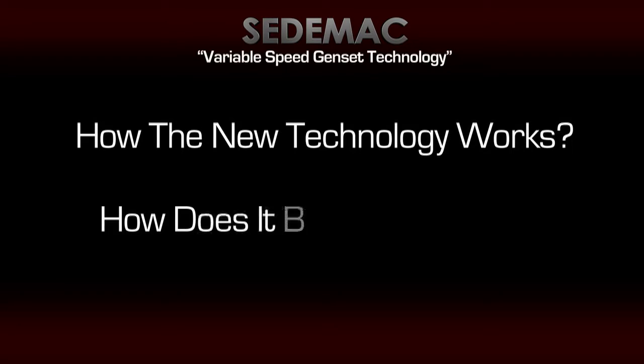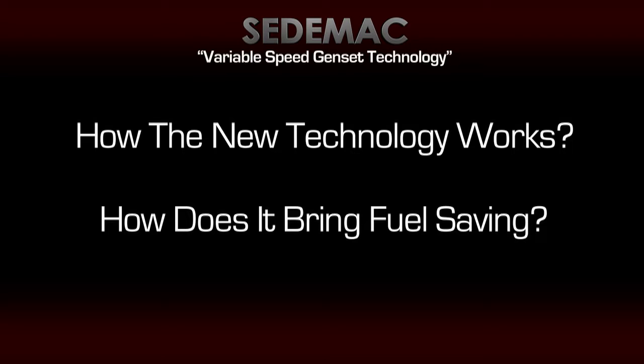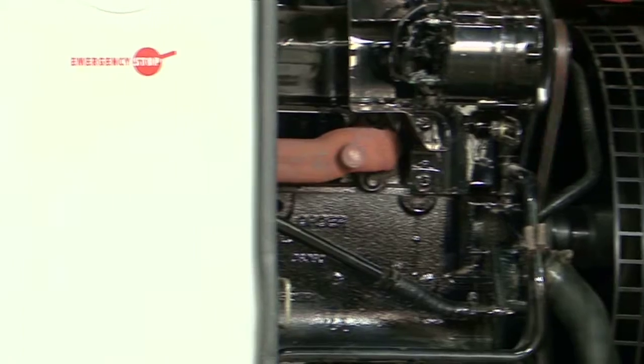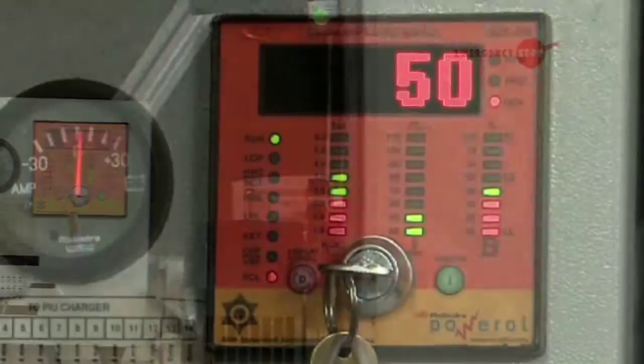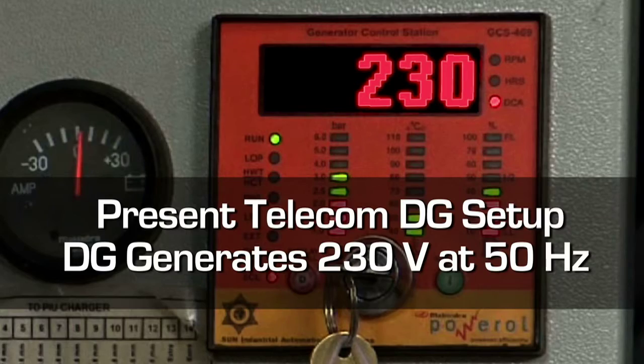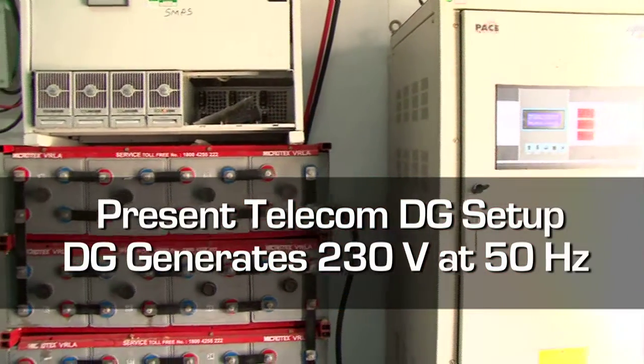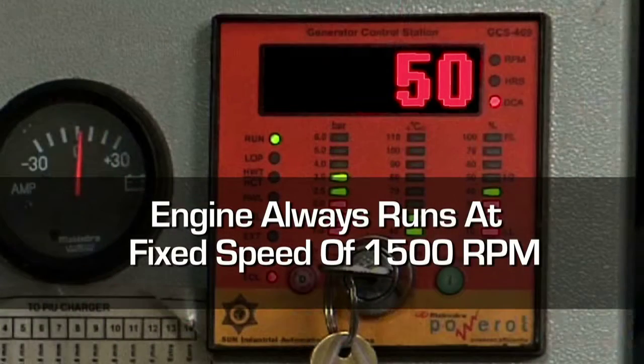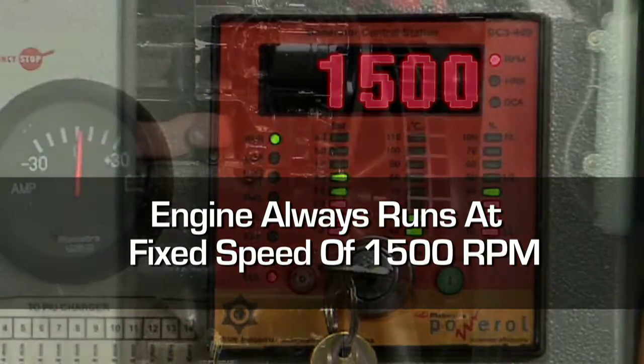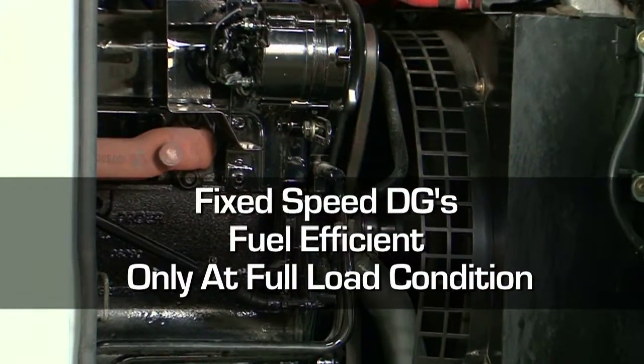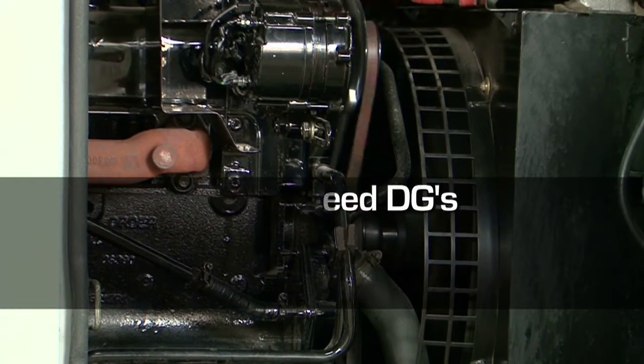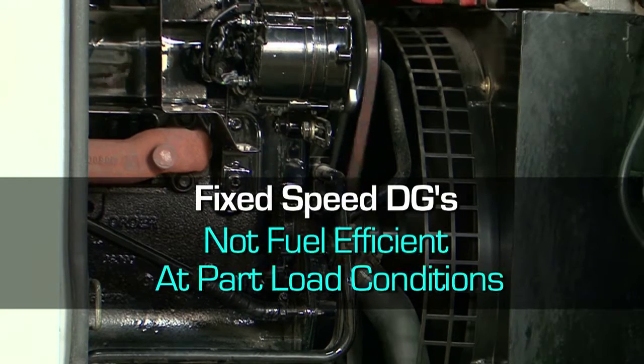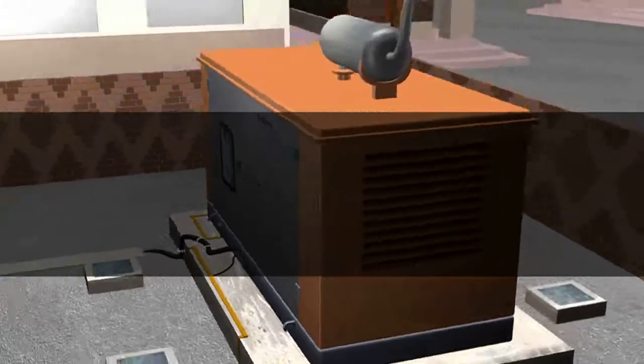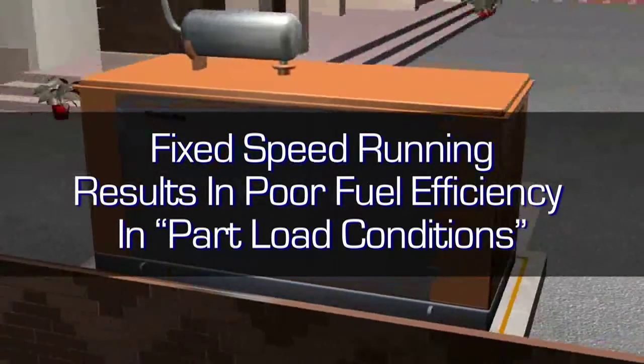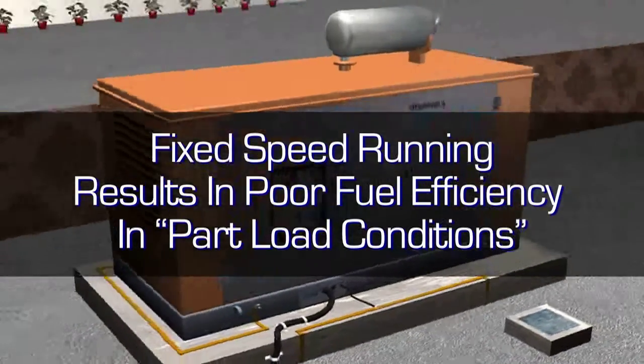You may be thinking, how does this new technology work? And how does it bring fuel savings? Let's have a look. In our present telecom DG setup, the DG generates about 230 volts AC at 50 cycles. And no matter what the load, the engine always runs at a fixed speed of about 1500 RPM. The fixed speed is rated for full load conditions, but it is not the optimum speed when the load on the DG is low. As a result, the fixed speed running results in poor fuel efficiency in part load conditions.